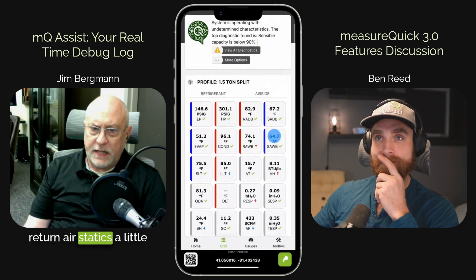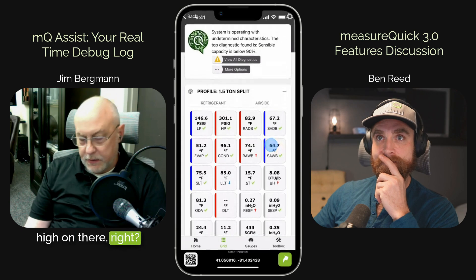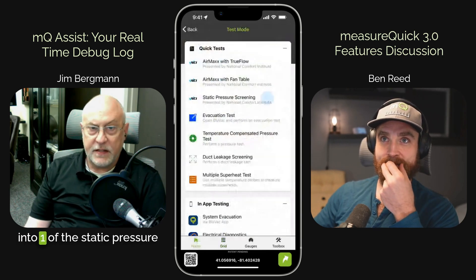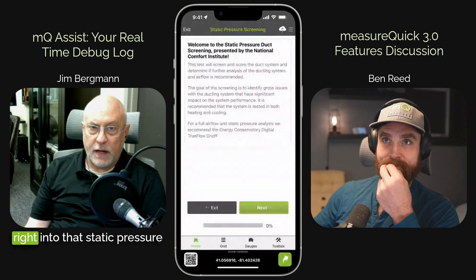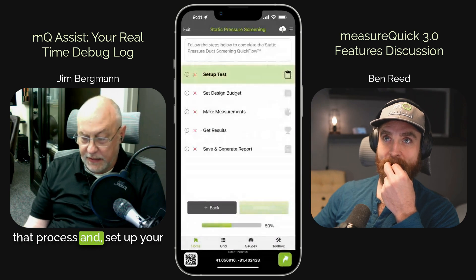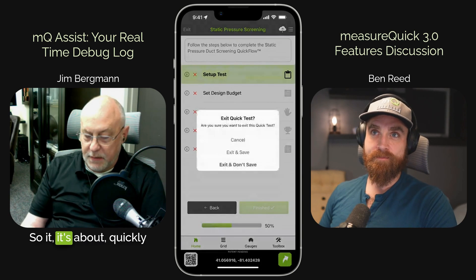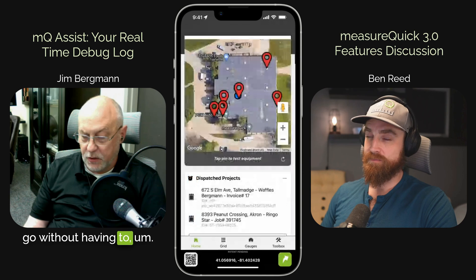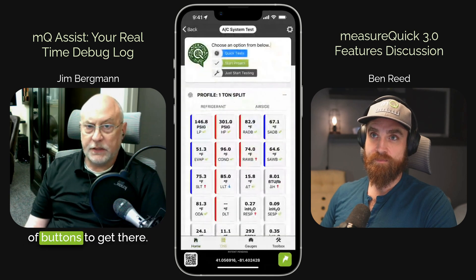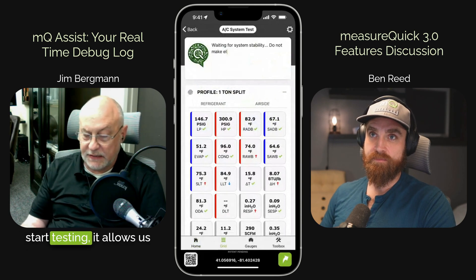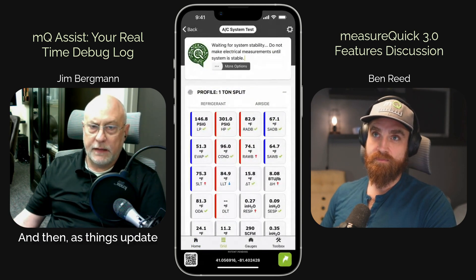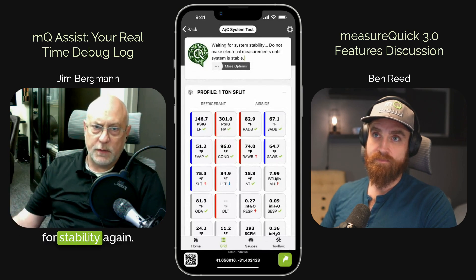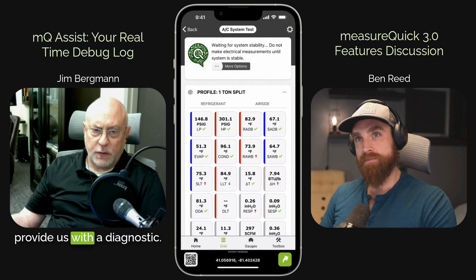You can see your return air static is a little high on there. There are also more options — if you want to do a quick test, you can go into one of the NCI static pressure screenings, jump right into that static pressure screening, set up your budget, and do those things. It's about quickly navigating the app and going where you want to go without having to tap a lot of buttons to get there. So if we want to start a project or just start testing, it allows us to get there quickly. And then as things update in the background, it changes the context. Right now it's waiting for stability again, and as soon as it's stable, it'll provide us with a diagnostic.